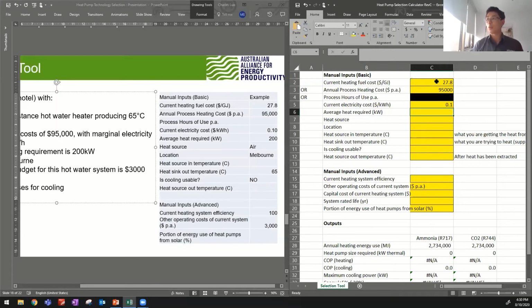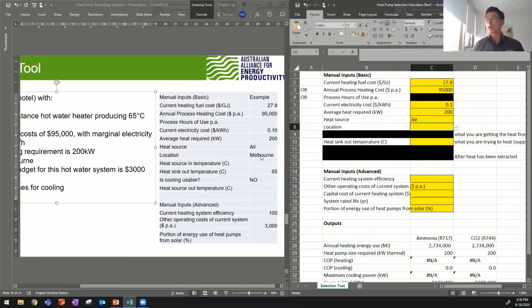The electricity cost is 0.1, 200 kilowatt heating. It's going to be an air source because there's no available cooling water, and you'll see a lot of these fields blacked out, because for an air source system there are no cooling sides - we're sucking in ambient air and expelling cold air as a result. This is in Melbourne, so straight away they'll take the average ambient air temperature of Melbourne for these calculations, and we want 65-degree water. The heating efficiency here - it's electric resistance, so it's 100% - and $3,000 is the operating cost.